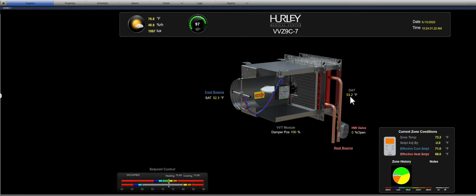Typically, we could have up to half a degree error between these two sensors. So we're looking at a tiny amount of heat gain in the ductwork as it's distributed in the building. This is the ninth floor. It's pretty close to the penthouse, so we don't see a lot of heat gain there. And we see that the damper is open 100%. Design-wise, this was designed for a 55-degree supply air temperature most of the time. So this actually is improved over design, and the unit damper is fully open to do all the cooling work it can do in the zone.